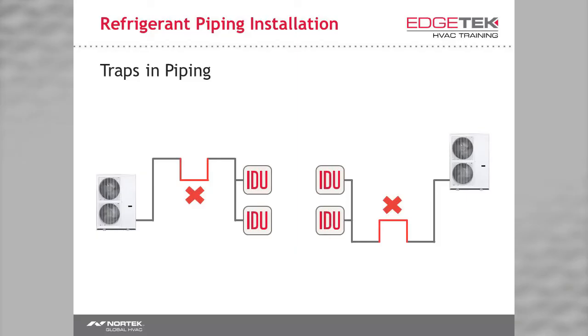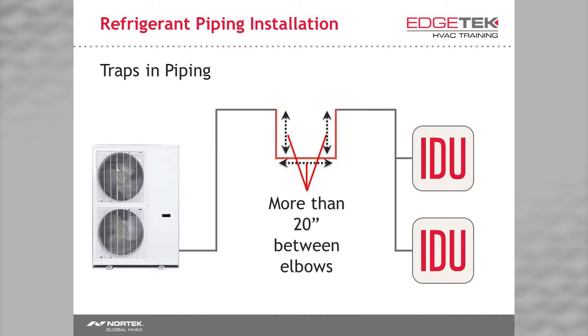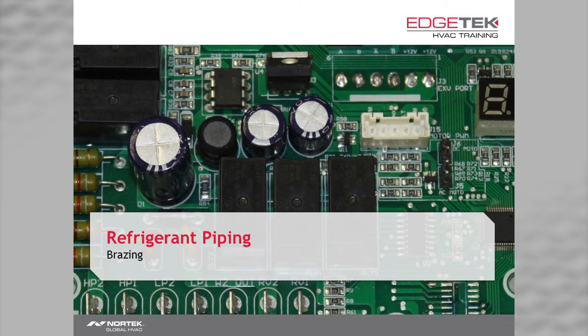Do we have other rules? Of course. Avoid traps in piping at all costs. For those that you can't avoid altogether, mitigate the trap by lengthening the bottom of the trap or use 45s rather than 90s. If you question an installation, feel free to send us a picture and we'll help you out. As far as mitigating the effects of the trap, also remember that you must have at least 20 inches between elbows. We are all brazing experts, right?